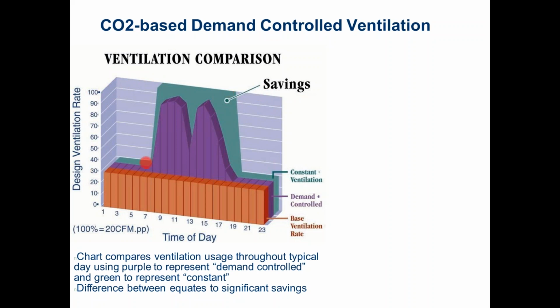Right, but a normal building goes occupied at 7 a.m. The damper goes wide open. It stays open all day long because nobody's ever interlocked it to a schedule, right? And then it shuts off at, what is this, 7 p.m. in this example. Boom. What demand control ventilation does is it uses CO2 sensors to detect the amount of people that are breathing in the space. The more people in the space, the more CO2 is produced, and the more ventilation air is required by code. Or you can think of it as the fewer people in the space, the less ventilation air is required by code. So if I have to have this code required amount of air, at my red little arrow up here, and if fewer people show up, I can throttle it back.